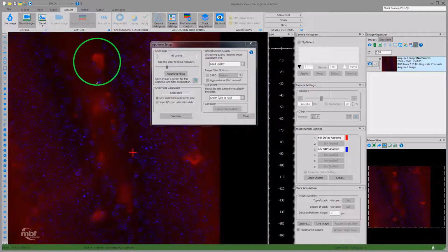Another problem that we often see is grid lines in the tissue like this. Now, those can result from many things, but one of the more common ones is the grid lines, or the shadow of the grid lines, being bleached into the tissue. This option, SABC, is Spatially Adaptive Bleaching Correction. Turn it on and set it to medium, and that will perform a software correction that smooths out and makes the dark areas brighter and the brighter areas darker, and makes the image look a lot more even and clean.